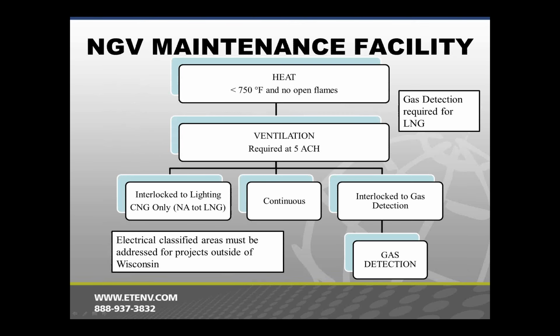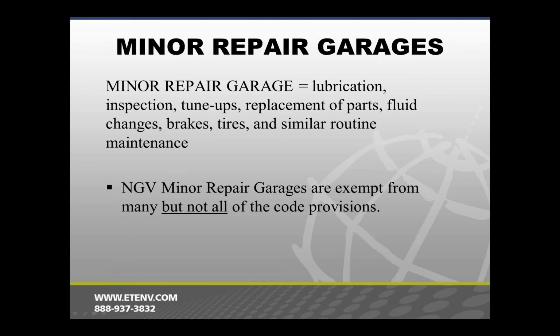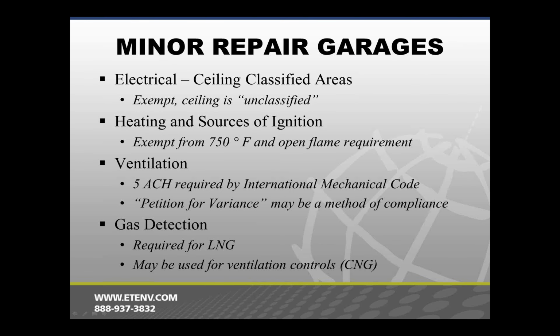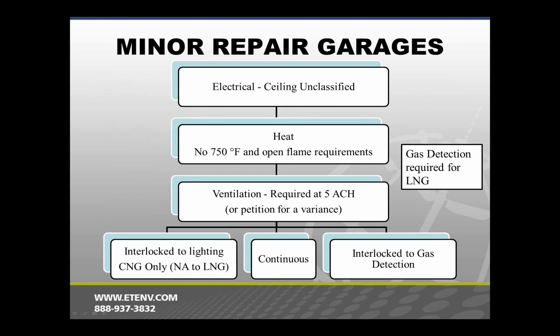We don't need to hit this too hard, but this is, in simple form, the natural gas vehicle garage repair requirements. Minor garage, Ted talked on that, so I don't want to repeat too much of this here. One thing about Wisconsin: for an electrically unclassified area at the ceiling, they're exempt from heating requirements in Wisconsin. Here's the one kicker in Wisconsin, the ventilation, in that the International Mechanical Code is adopted by the state, and there's actually no exception for a minor repair garage to deal with this 5 air changes per hour. But there is a petition for variance process that the state officials have said they would certainly consider in this case. Gas detection is not required except for controlling a ventilation system, or it is required for LNG because it's non-odorized. And again, here's a quick summary of those requirements.